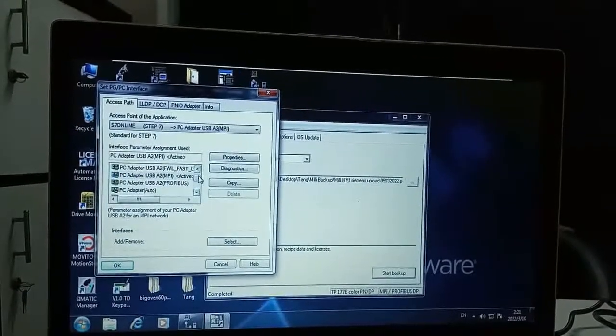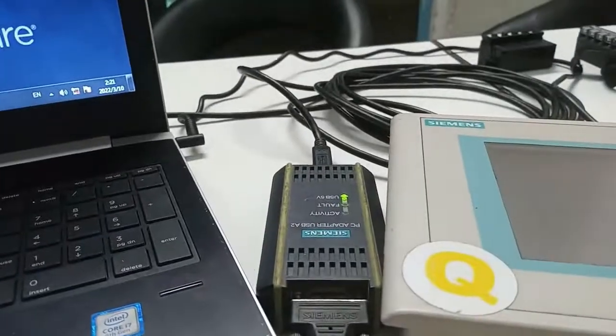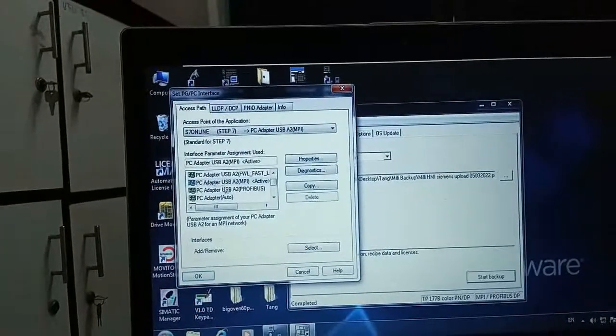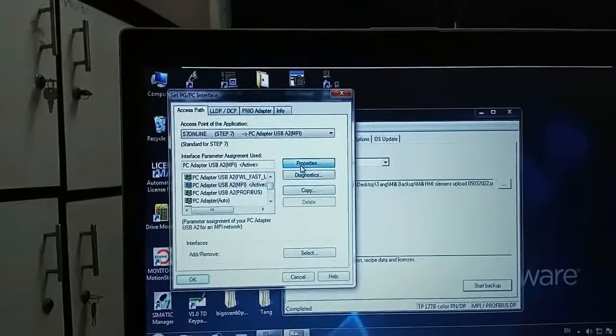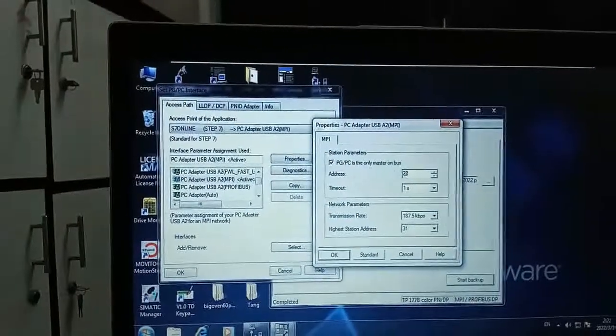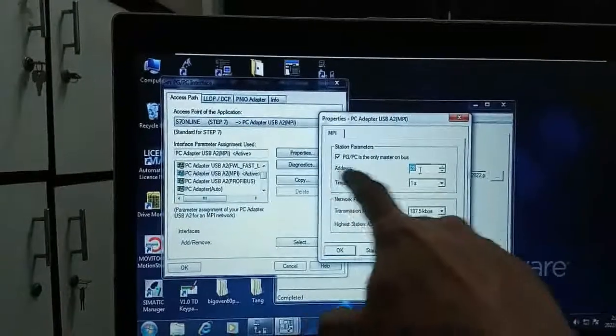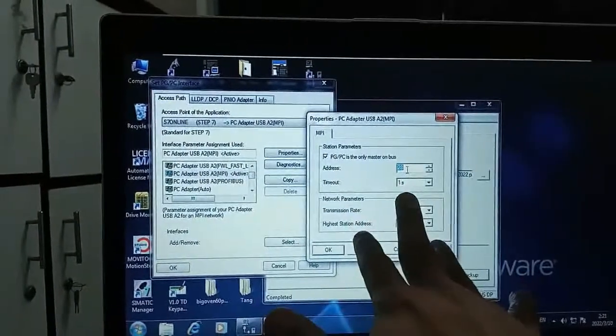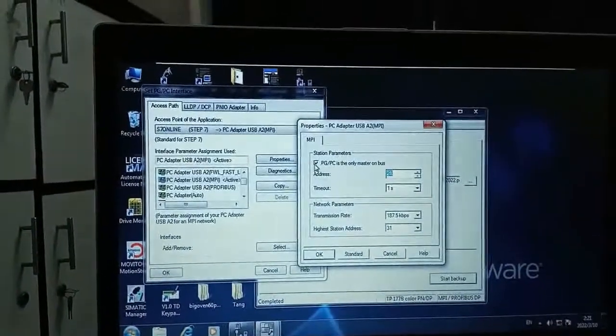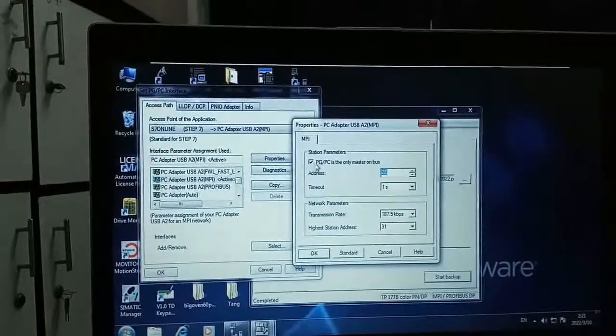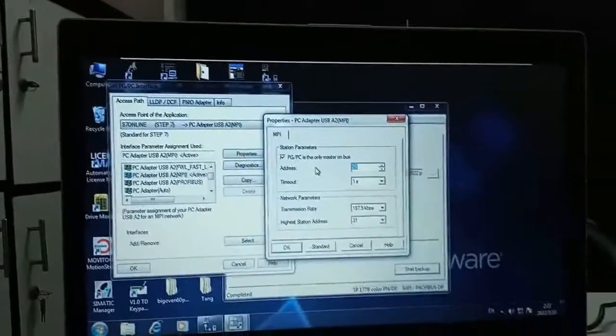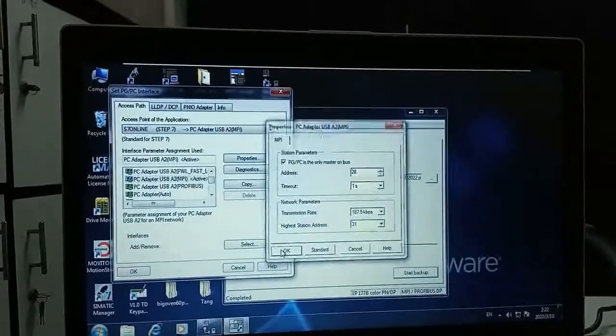So I am using Profibus PC adapter MPI cable. So I will select USB A to MPI option and go to the properties. Here I will provide address of this and I will tick mark PGPC interface is the only master in the bus. Then select OK.